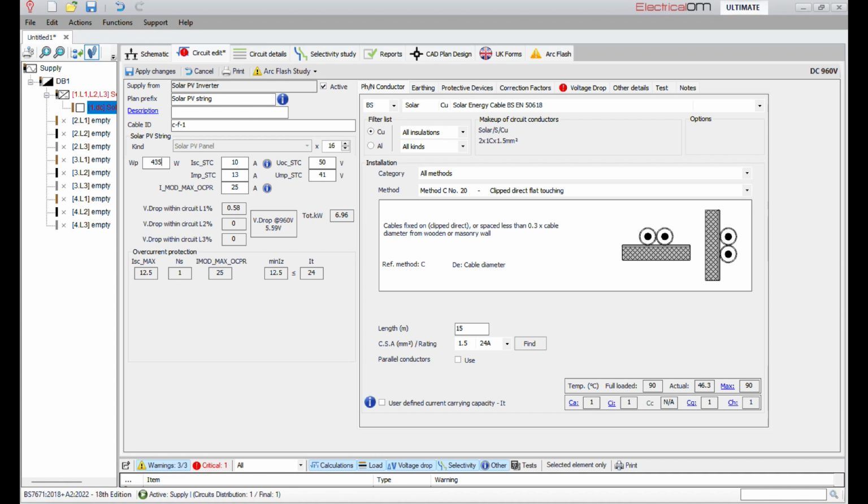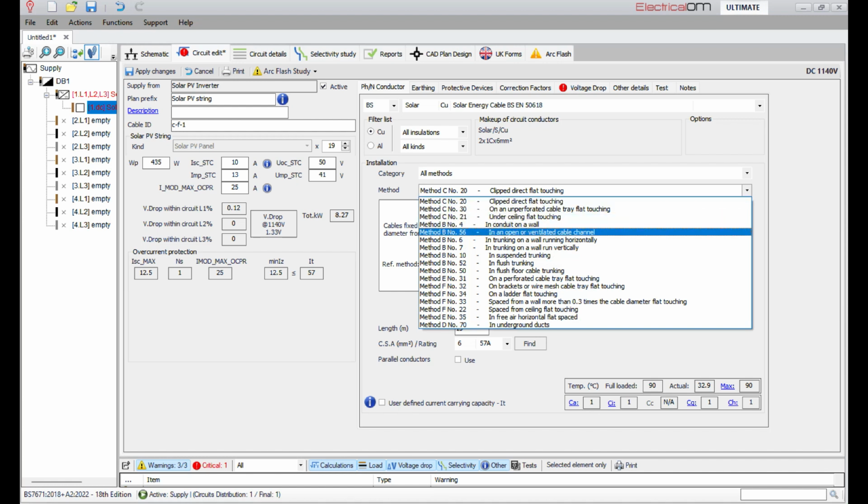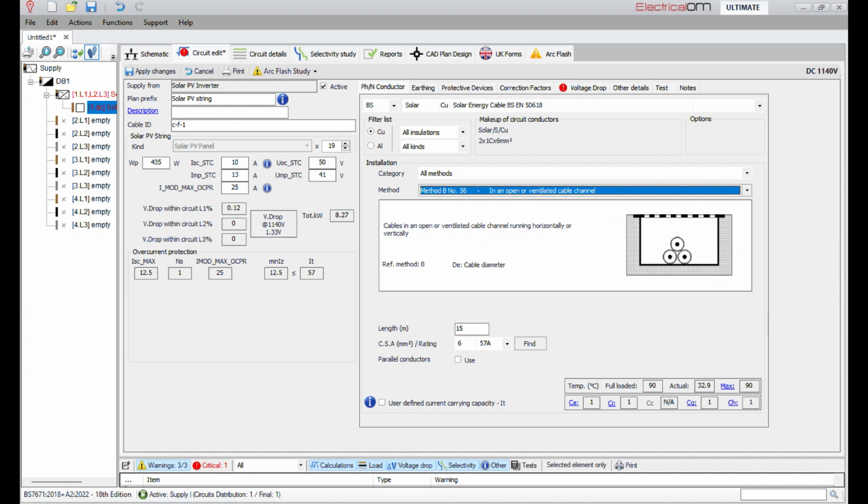So we're popping strings in here. I'm trying to balance the strings out against our inverter rating across the three phases. So I'm going to run with 19. That roughly balances out to 25 kilowatts of generation based on those panels. And I'm going to change our cabling type for the strings to 6 mil, set an approximate length, and we can set these. I was thinking of using this option because they sit inside some of the rails on an installation, but I've gone for the tray option in the end because they are set against that as well.